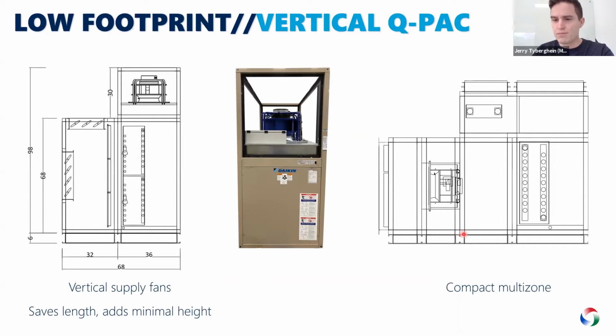On the right is a compact multi-zone unit. I just like to show this example because while multi-zones are not as popular these days, when you're replacing them, the designs from back in the day, they really got compact, probably invalidated some airflow rules, but we can take QPAC ECM fan arrays, really shrink down the unit, save a lot of footprint.